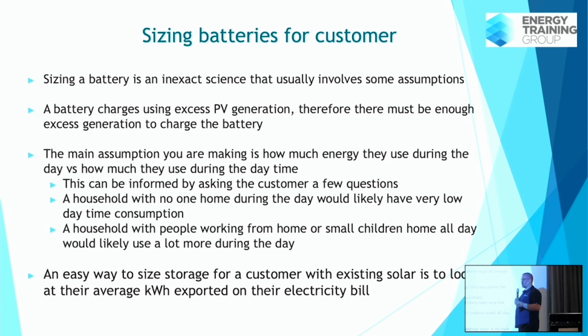If they do have solar, there's one really easy way you can do it. Get the customer's bill, look at their export. If they are averaging 20 kilowatt hours of export a day, you could probably install about a 10 kilowatt hour battery, and you'd know that generally it's going to cycle once a day. You don't want to install a battery for a customer that's only charging to 50% every day, because the customer's going to waste an awful lot of money buying a battery that's too big for their site.